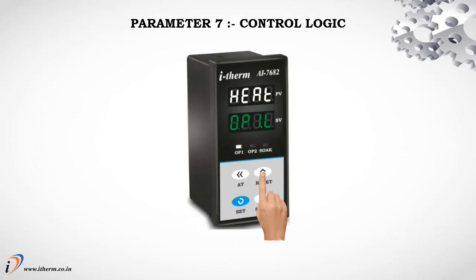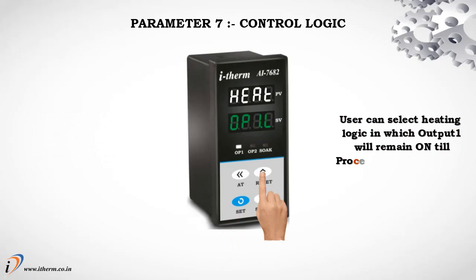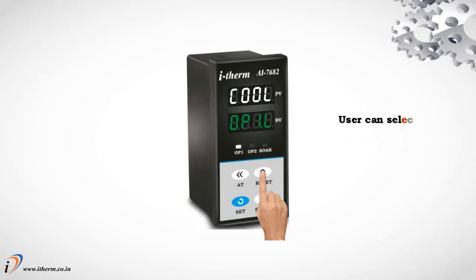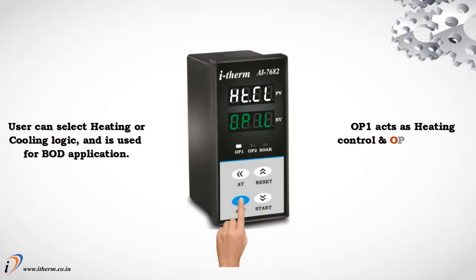Parameter 7, Control logic. User can select heating logic in which output 1 will remain on until process value is less than set point. User can select cooling logic in which output 1 will remain on till process value is more than set point. User can select heating and cooling logic, which is used for BOD application. Output 1 acts as heating control and output 2 as cooling control.